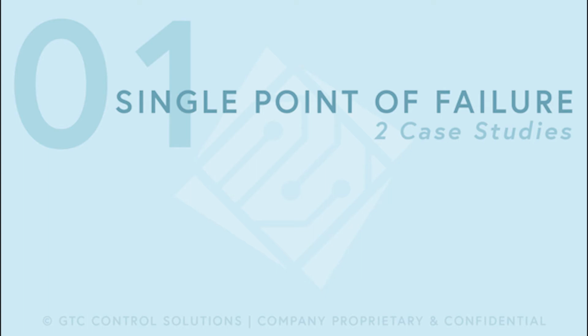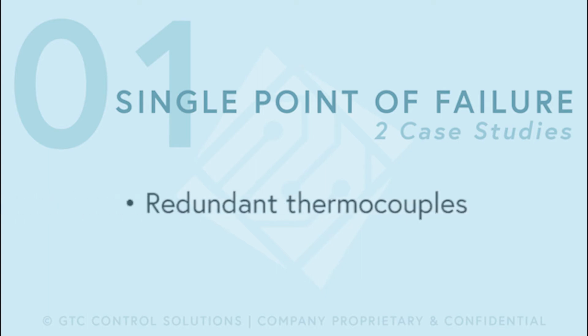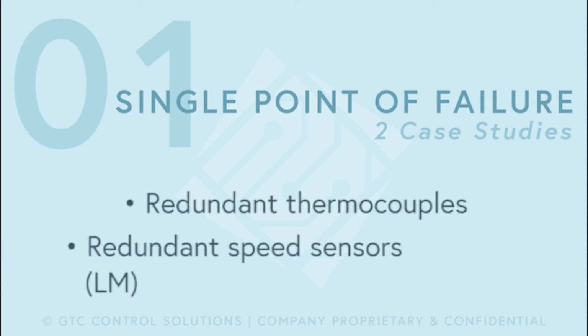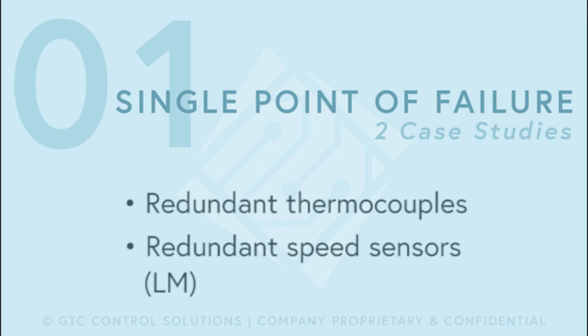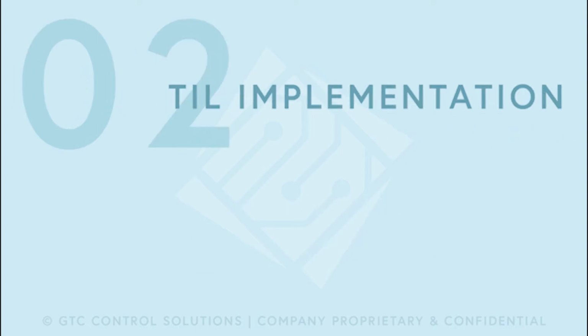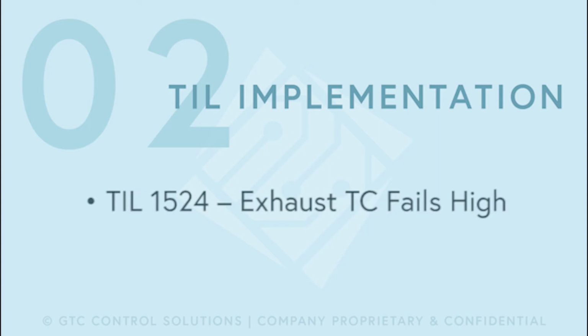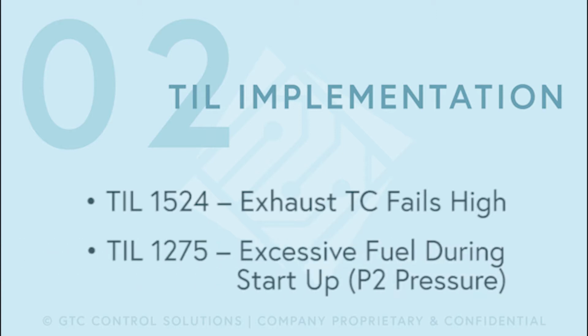What are we going to discuss today? We will be presenting the single point of failure, two case studies, one about redundant thermocouples and another one about redundant speed sensor. It is about an LM unit, aeroderivative unit, but depicts dramatically the importance of detecting single point of failures. Then we will discuss TIL implementations. Two TILs in special, because they apply to all gas turbines. TIL 1524, when one exhaust TC fails high, a particular case of a single point of failure that resulted in a TIL, and then TIL 1275, excessive fuel during startup, the P2 pressure control.